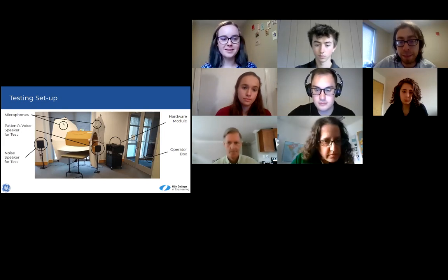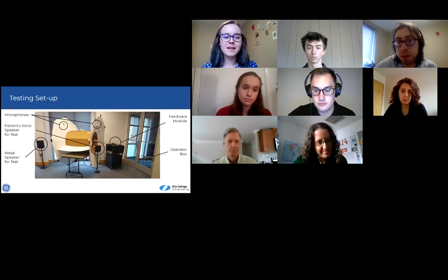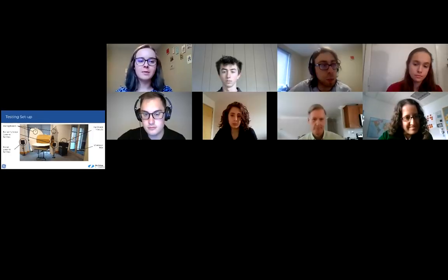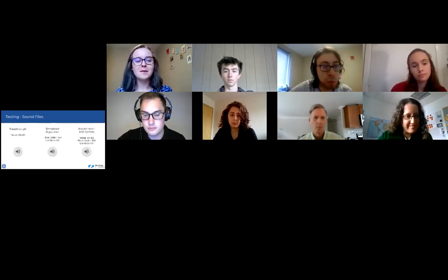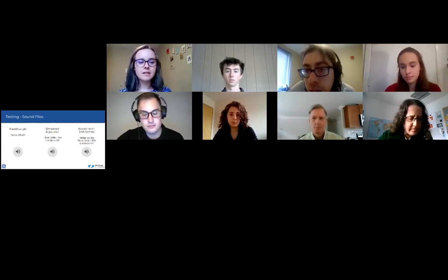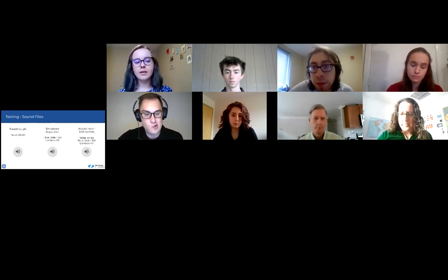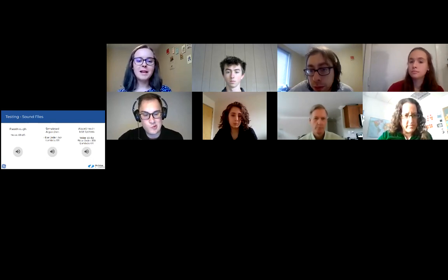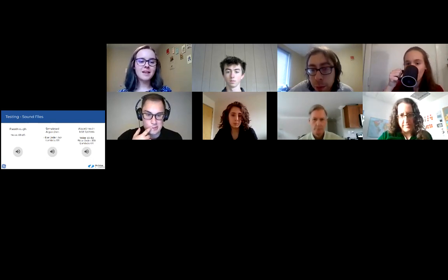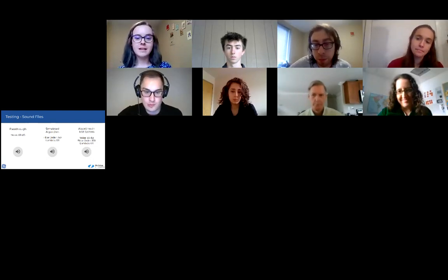So as you saw in our snapshot presentation, this is a picture of our testing setup. And we'd like to share a few audio files with you now that we collected from some simulations as well as from this setup. So for these samples, the inputs to the system are first a recording of CT gantry noise that we received from our liaisons at GE Healthcare. And then the other input is a simulated patient voice, which is actually me talking, saying Harvard sentences, which are sentences that are widely used in audio intercom testing because they are phonetically balanced for the English language.